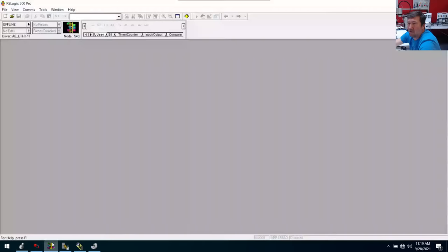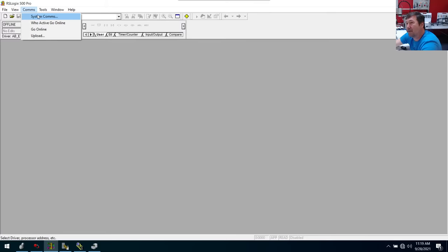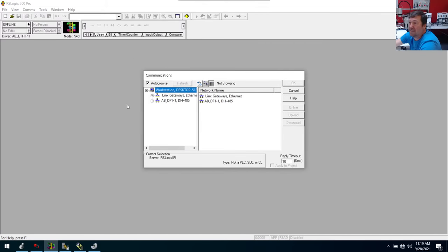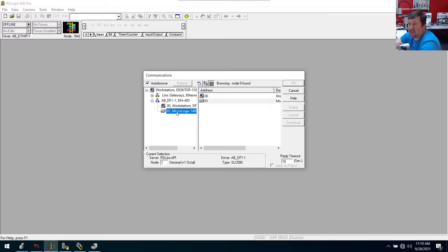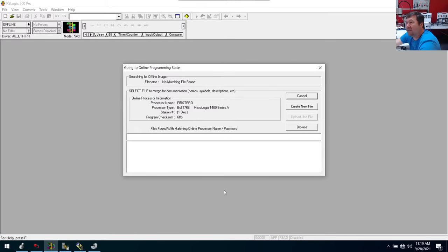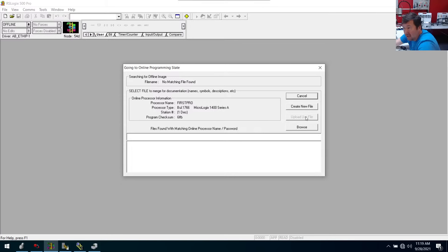We're going to close this out and go over to RSLogix 500. While it's changed a little bit, we still have Communications, and then in this case it's system communications — this is going to give you all your options again. And then we're going to have our MicroLogix 1400. Only this time we didn't get a communications timeout — we have the Go Online button. I'm just going to hit Go Online, and then you're going to end up with this prompt right here. We can cancel, we can create a new file, we can upload a file, or we can browse. What this means is the file that we have open doesn't match what it sees in the processor.